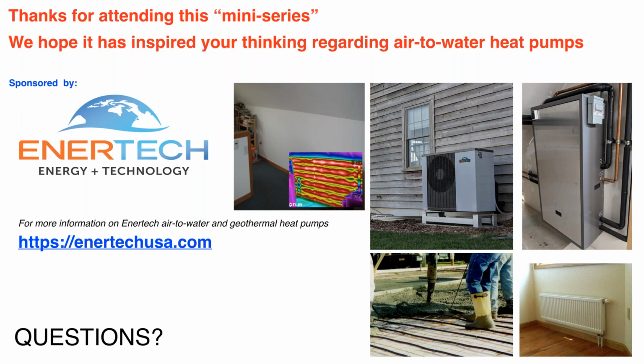As I say, when we were talking about the heating only application, we talked about the high thermal mass slab. During defrost, energy would come out of that slab. But remember, that does have the electric indoor unit. It does have the 9 kW resistance heat. So with a warm floor type of system, you don't have as much thermal mass. There still is significant mass there, but if necessary, the electric element would operate in defrost mode. If it is the dual fuel version of the Advantage heat pump, you do need to have that TurboMax tank there as a thermal mass that possibly would be accessed during defrost.